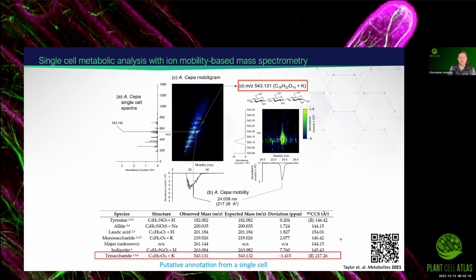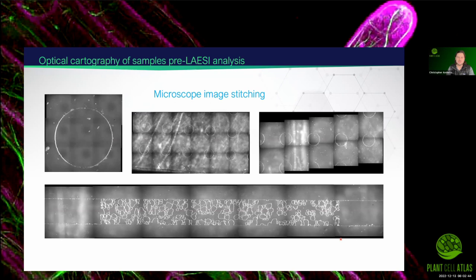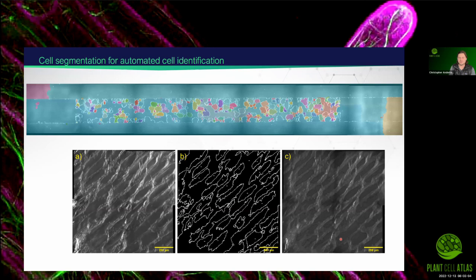One of the things we were able to do — using ion mobility data, which is an orthogonal method where we measure the actual size of a molecule before measuring its mass — is measure multiple molecules from single cells at a time and have high confidence in their molecular annotations. Not only could we do individual microscope images, but we could do image stitching and autofocus if our sample had topography, which helps keep the laser in focus. Through cell segmentation and automated cell identification using machine learning plugins in ImageJ, we're able to identify in an automated fashion where cell centers are, so we can image cell by cell and move much faster.